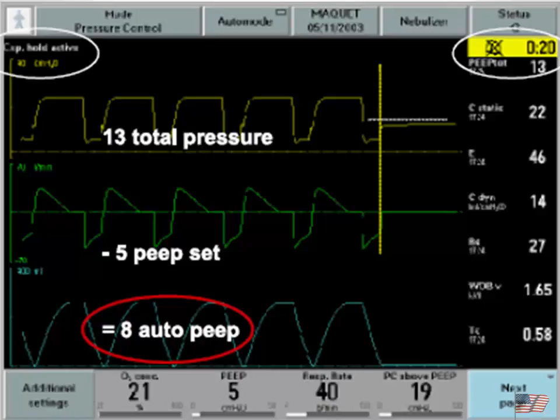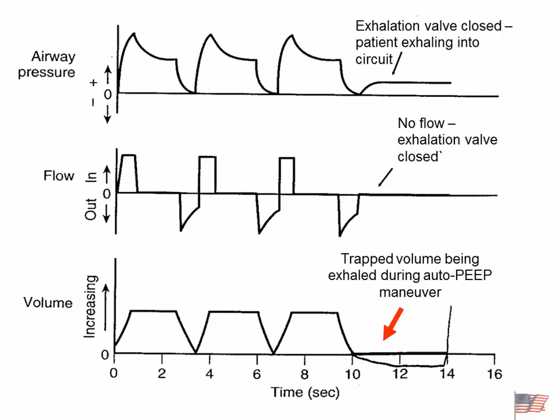Again, the exhalation valve closes. We're normally on 0 set PEEP. We rise up into whatever that distance is, how much exhale volume we have. And you can see that exhale volume being measured on the volume tracing.